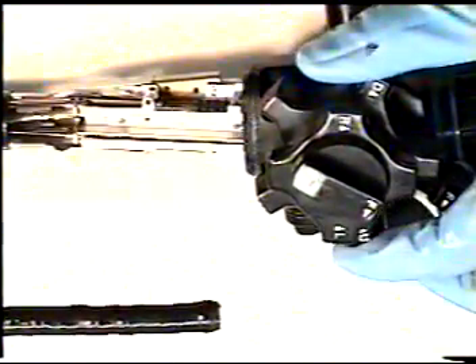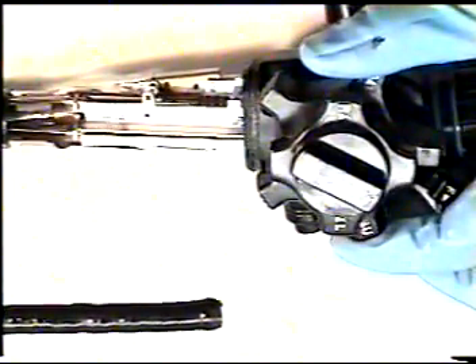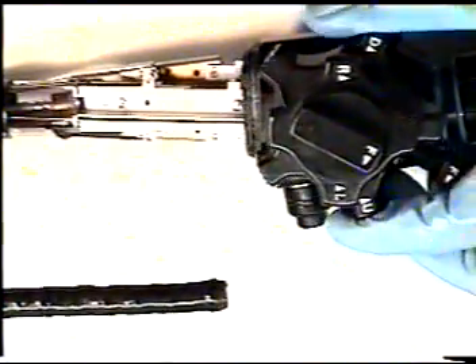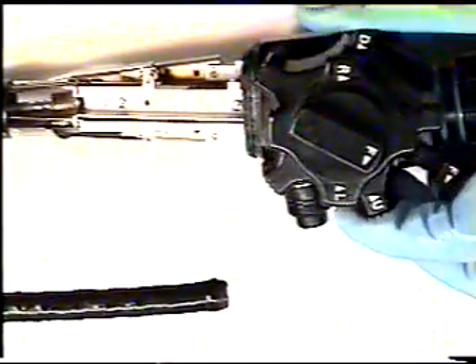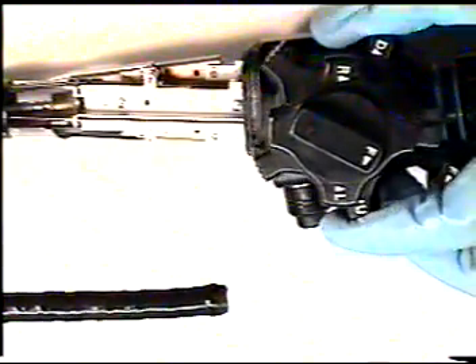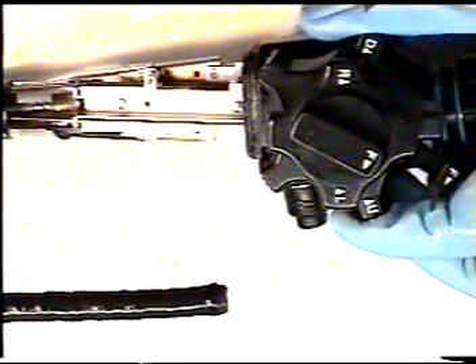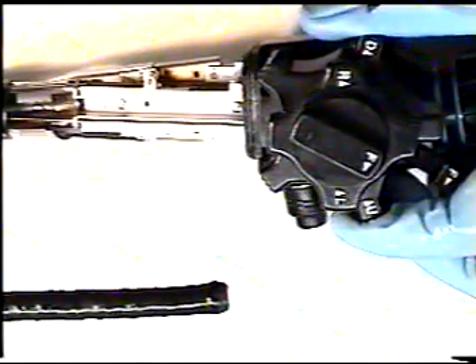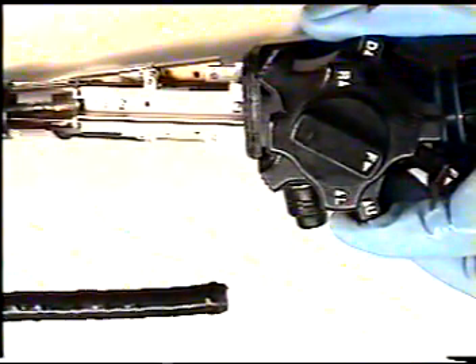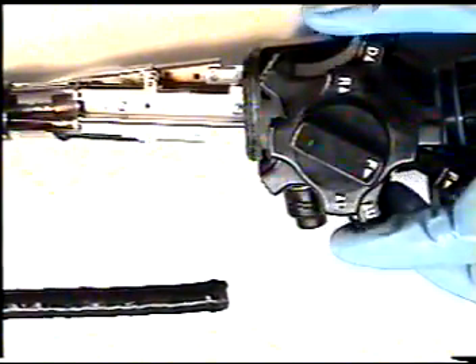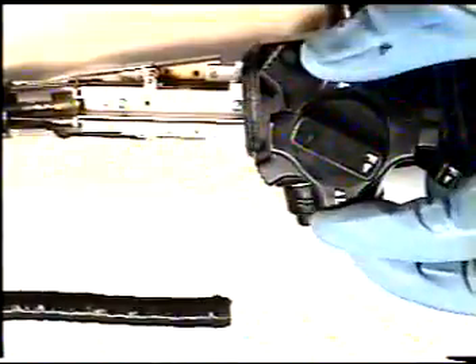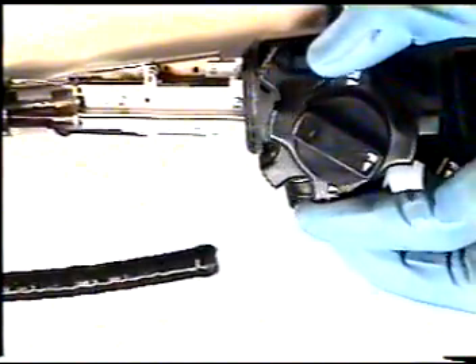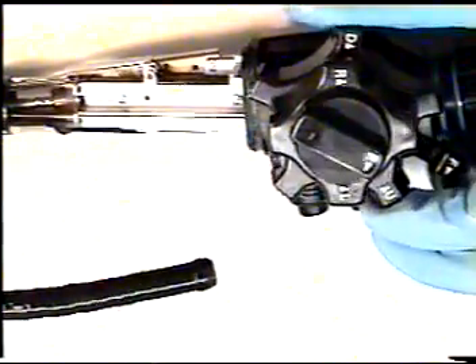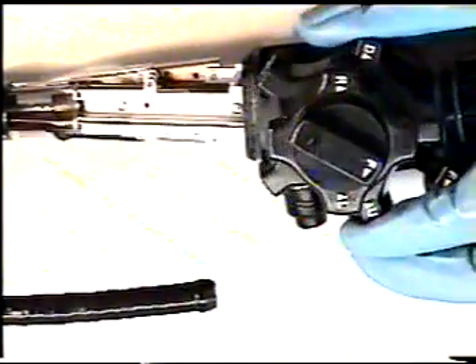Once all wires and coil pipes are in place, we will now check for play before reassembly. When the knobs are turned, just barely, the tip should also deflect at the same time. If the knobs are turned and there's no deflection, you'll have to repeat procedures to adjust for play. It goes for both up, down, and left, right. Tip should deflect as soon as knobs are adjusted.